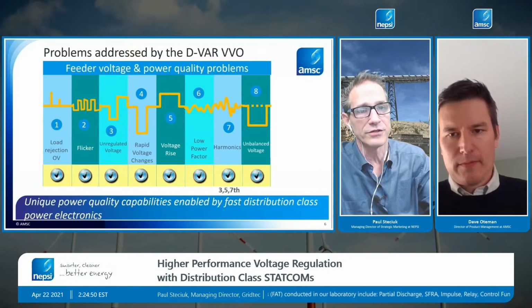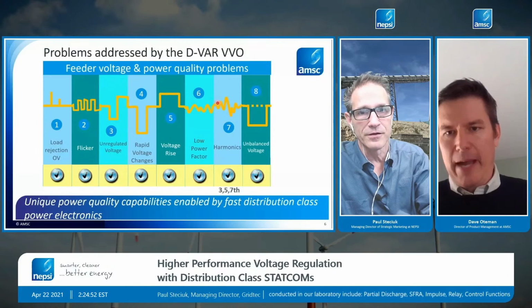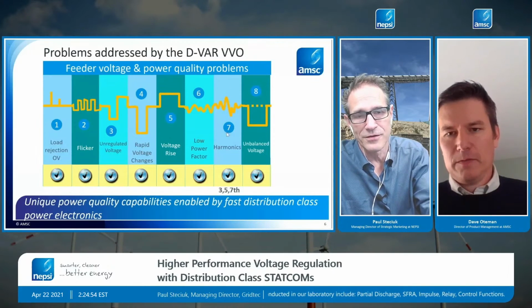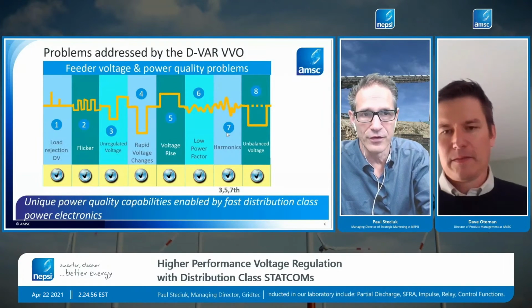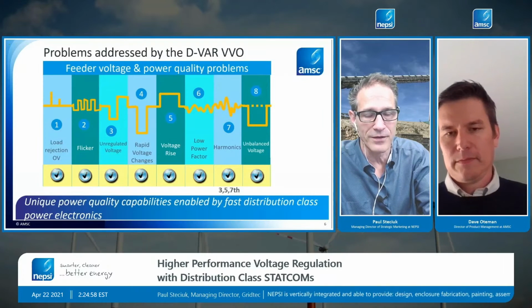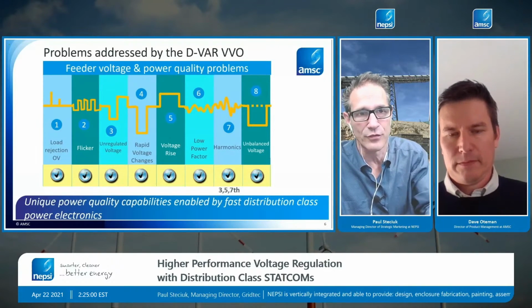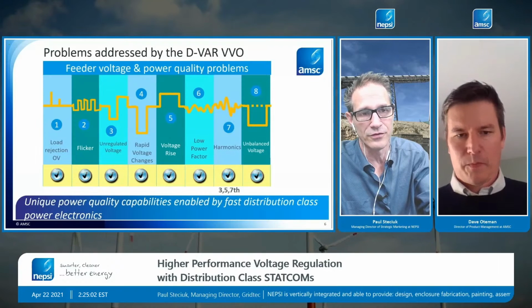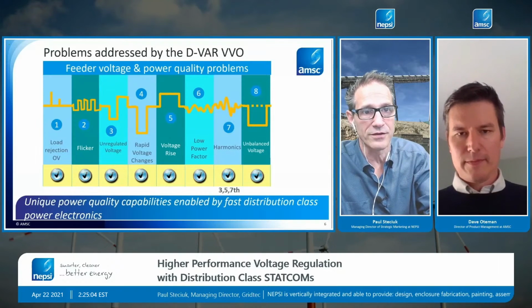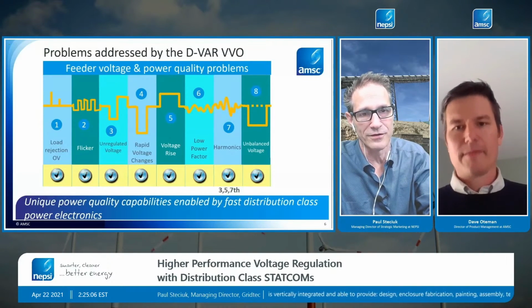Number 7, in relation to harmonics there. Capacitor banks cause resonance, and this VVO system is not a capacitor bank. It doesn't have a capacitive reactance, and therefore it doesn't contribute to a concern for resonance like a capacitor bank does.